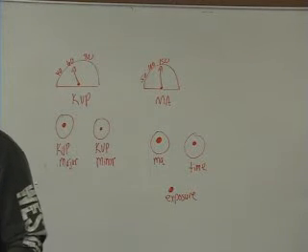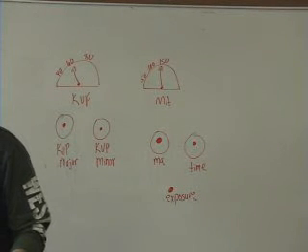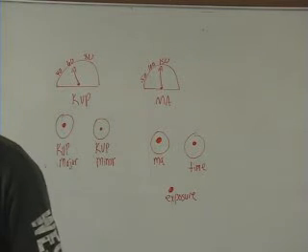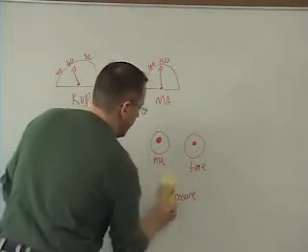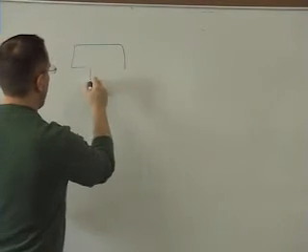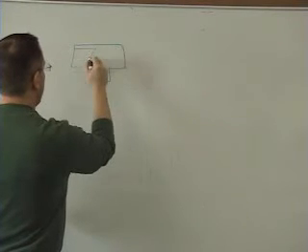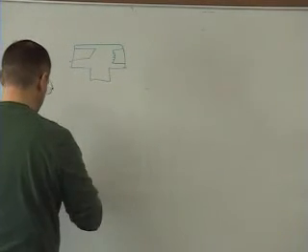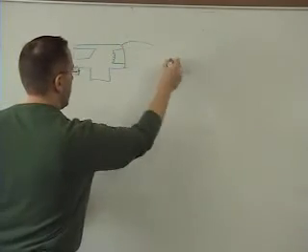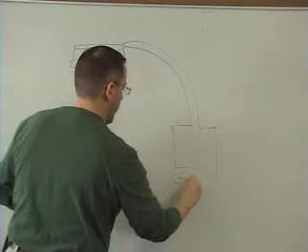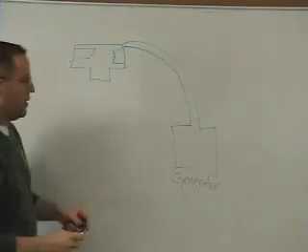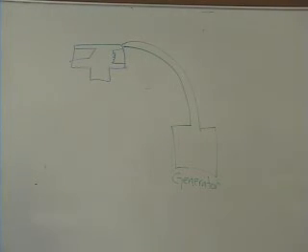All right, you also see a picture on page seven of the X-ray tube, and there's some wires going towards it, and there's a generator. The generator is what gives you the power to produce the X-rays. So here's your X-ray tube with the anode and the cathode. You've got all these cables going over here to the generator. Because you need to get up to pretty high voltage to produce radiation.